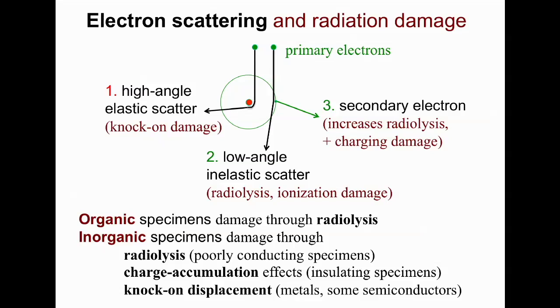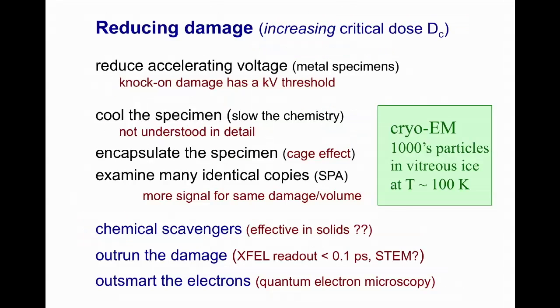In non-conducting specimens, most of the damage arises from inelastic scattering. This process transfers energy to atomic electrons, breaking chemical bonds and generating secondary electrons that create even more damage. Together, these effects are known as ionization damage or radiolysis. For a beam-sensitive specimen, knock-on damage does occur, but is insignificant compared to radiolysis, so reducing the accelerating voltage has little effect. Instead, we can lower the specimen temperature, which generally reduces the rate of radiolysis.